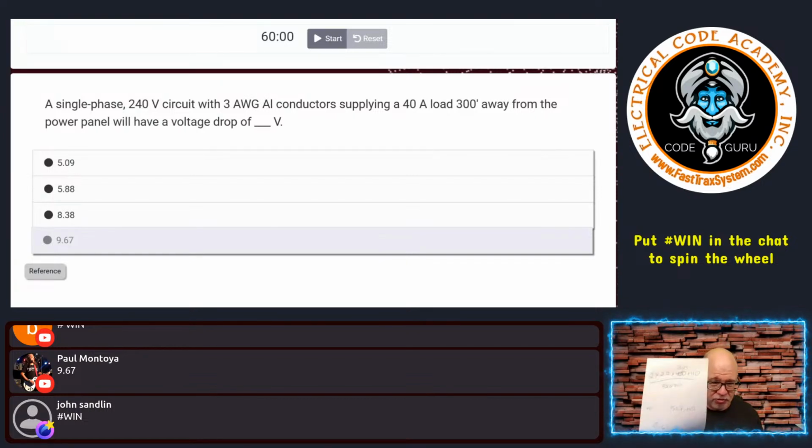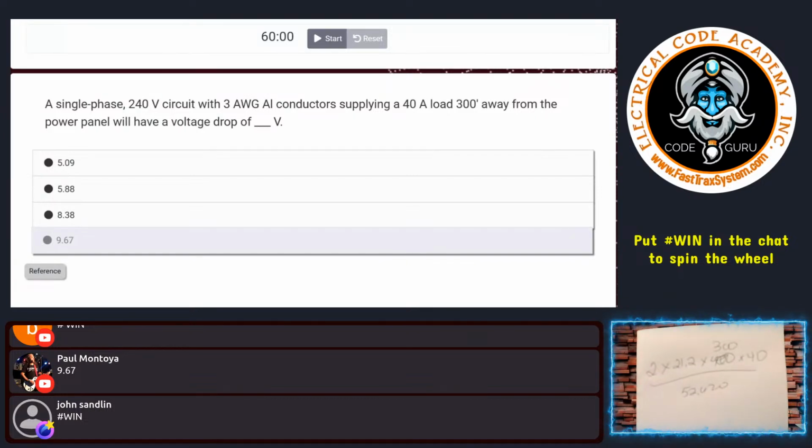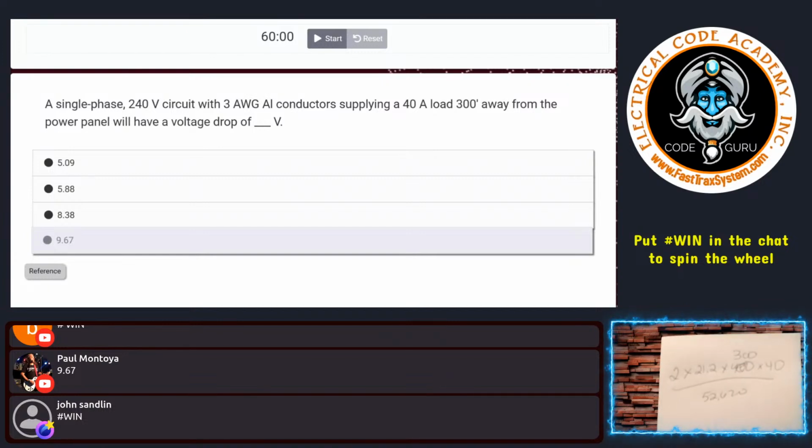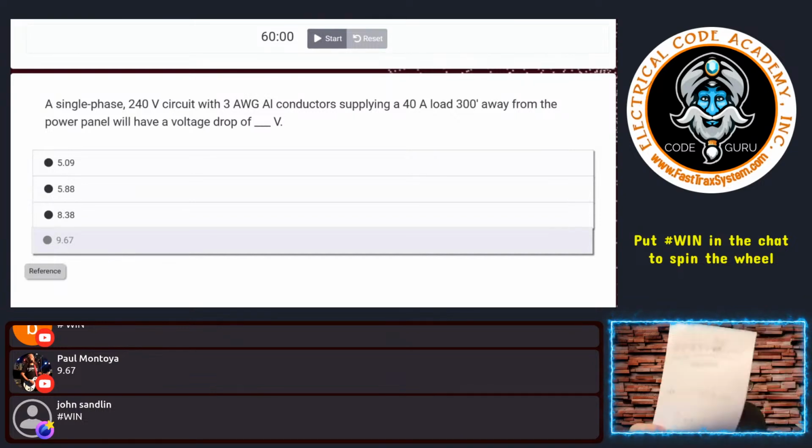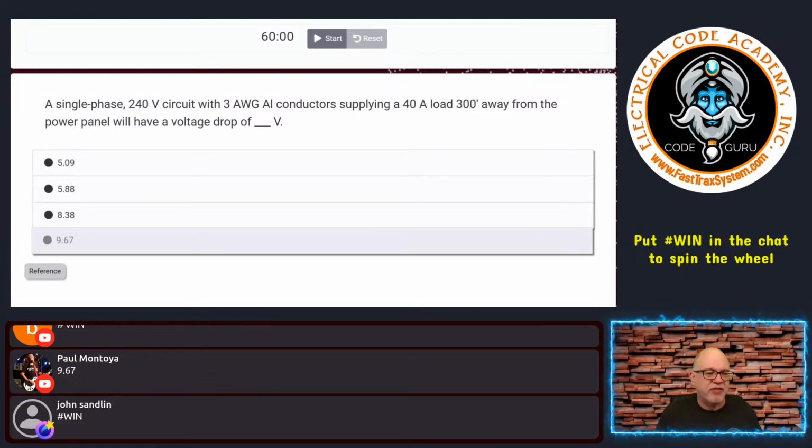Okay. So I did the math, right? 2 times 21.2 times 300 times 40, okay, which was 508,800. And then you divide that by the circular mils of the conductor that they presented in the question. And that is how we got 9.669, which rounds to 9.67, or the best plausible answer on the screen.